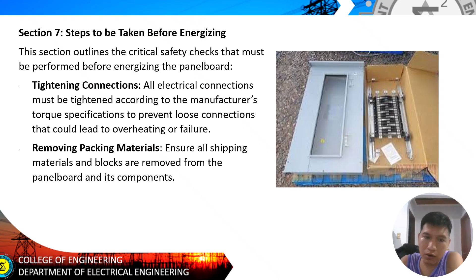Removing packing material: ensure all shipping materials and blocks are removed from the panel board and its components before we energize the system. Because if we don't tighten them, it might trip or get burned. So make sure there's no overheating or failure in what we're doing. There will be an instance when the connections aren't tightened, and it operates okay at first, but after maybe 5 days, it gets burned. So make sure our connections are okay.